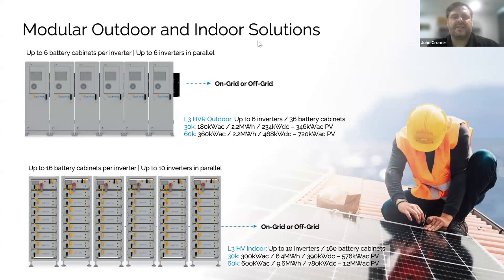So you can do a total of 6 inverters with 36 battery cabinets. For 208 3-phase, that's about 180 kW of backup power with slightly above 2 megawatt hours of battery, and a solar array that ranges from around 230 to 350 kW in size. Of course, you could always have different blocks of systems, stacked, backing up their own service points, but that's a different discussion outside the scope of this webinar.